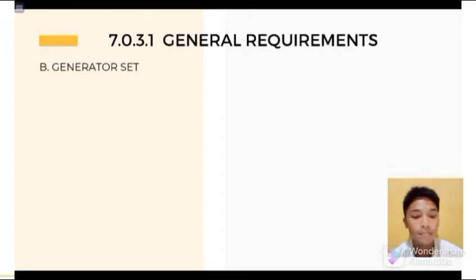So for the number 4, battery, power, and dampers. Where a storage battery is used for control or signal power or as the means of starting the prime mover, it shall be suitable for the purpose and shall be equipped with an automatic charging means independent of the generator set, where the battery charger is required for the operation of the generator set. It shall be connected to the emergency system, where power is required for the operation of the dampers used to ventilate the generator set. The dampers shall be connected to the emergency system as well, same as the internal combustion as prime movers.